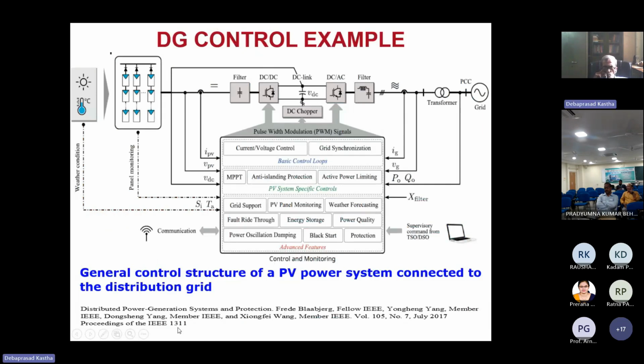Just coming to some specific examples, suppose you have a PV array. What are the controls that need to be done? At the very basic level, you have the current voltage control and grid synchronization. On top of that, you have MPPT control, then anti-islanding protection that I have not discussed, and active power limiting. This is what you can call primary control. Then on the next level, you have grid support, that is LVRT or other kinds of support, PV panel monitoring, weather forecasting, fault ride through, and energy storage, and these are the secondary control. Of course, protection is not a secondary control.